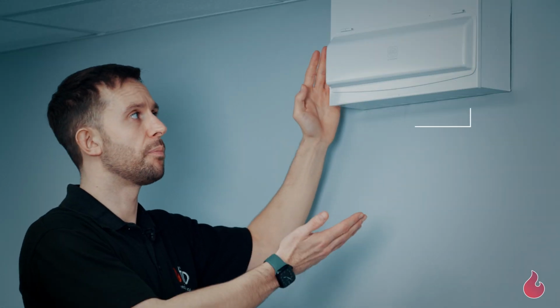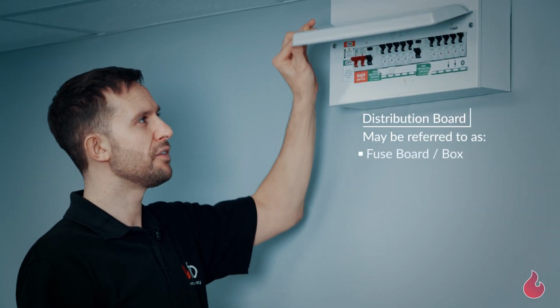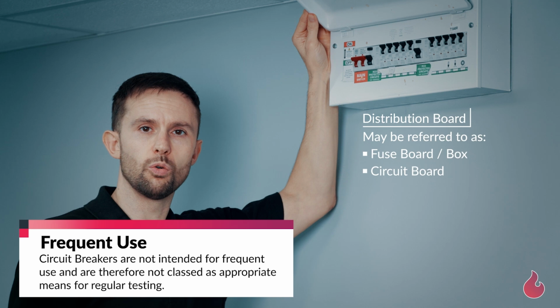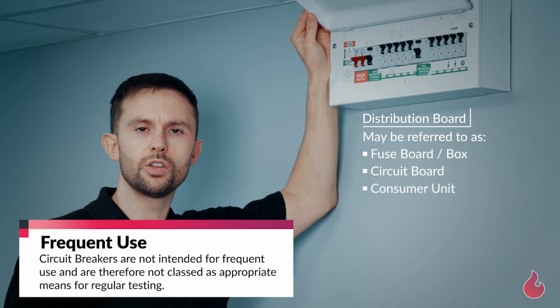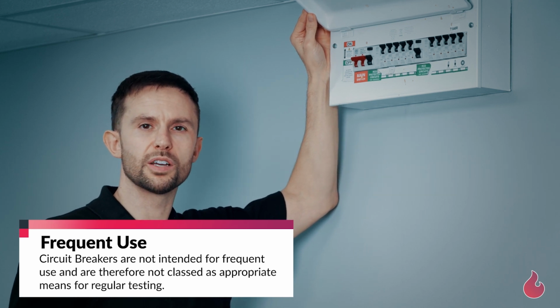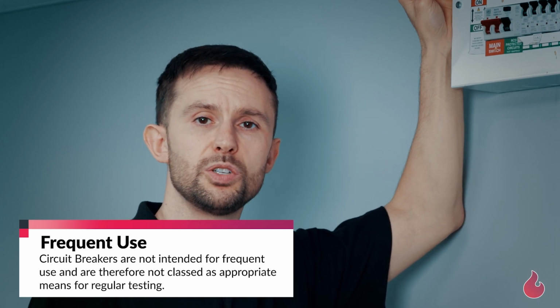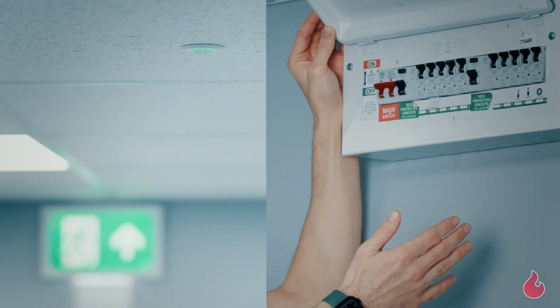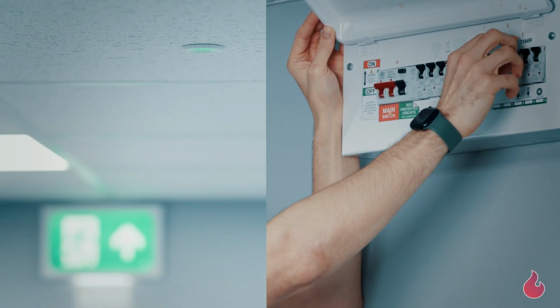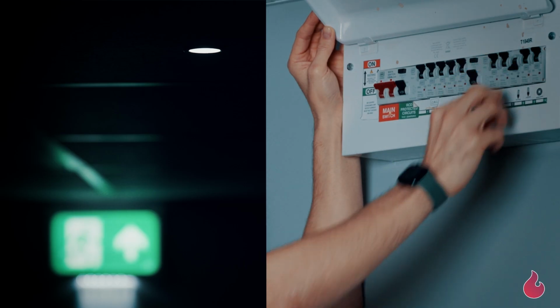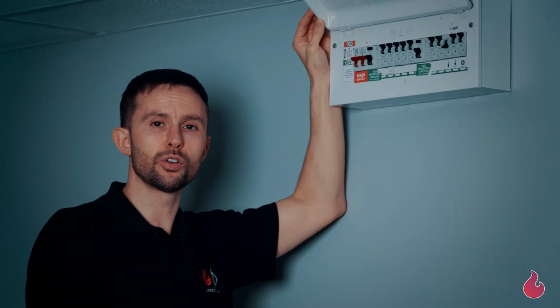Before carrying out your monthly emergency lighting check, it's important to understand where your fuse boards or distribution boards might be located. This is an example of a distribution board, and if I lift the lid here, you'll see all the fuses or circuit breakers. It's important to ask your electrician or service provider to mark which fuses need to be switched on or off in order to test your emergency lights. So my distribution board has already been marked, and I'm going to switch off the fuse here for the lighting. And what that's going to do is switch off the power to the lights in the corridor and move the emergency lights over to battery power.